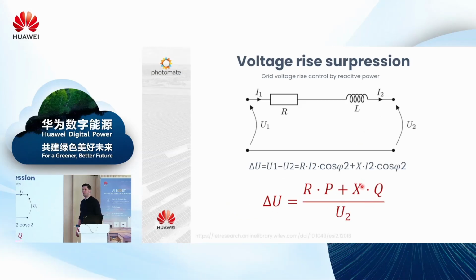And if we just enable the voltage rise suppression function, our inverter will use this value to reduce the voltage difference. So it will consume some part of reactive power. So this power here will have the minus sign, and then it will allow you to reduce this voltage by a few volts. And this is the solution of your problem in residential. The owners of residential installations are not paying for the reactive power right now, or not paying fines for this, so you can easily use it.